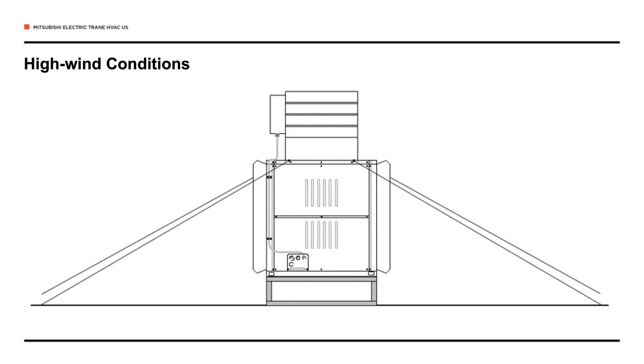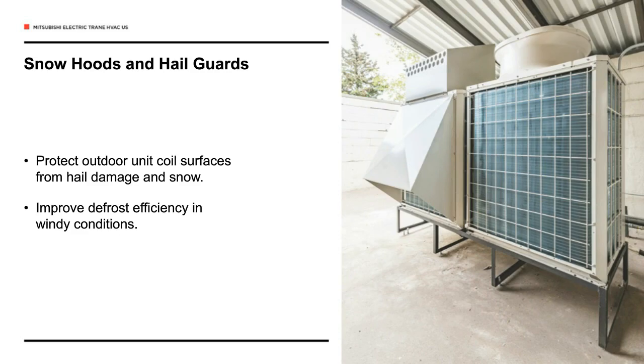You want to make sure that the units are secure. Snow hoods and hail guards are a good idea depending on where the units are mounted. Those two units there, the one on the left has both the hail guards installed and the snow hood installed. Probably wouldn't install those in this application because it's got a roof over it. Generally that's for areas where it's open to the weather.